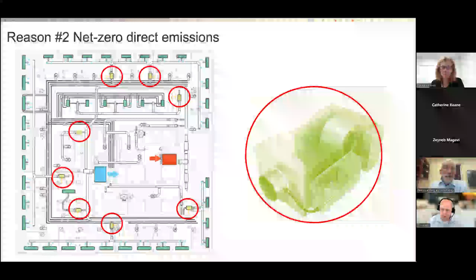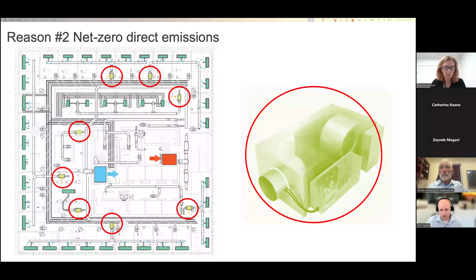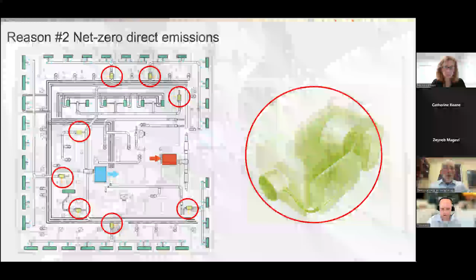The thermal ventilation systems are fully decoupled here, allowing the efficient movement of thermal energy to chilled beams using water to move that energy. Tom, do you want to add anything here? Sure. When we were designing the mechanical system for this building, load reduction was the priority. So using a dual wheel DOAS serving fan power boxes serving chilled beams allowed us to use smaller dedicated outdoor air systems. So the fan power boxes get return air locally to drive the chilled beams. And back to you, Dennis. Thanks, Tom.